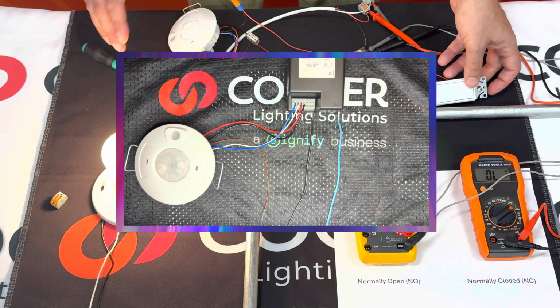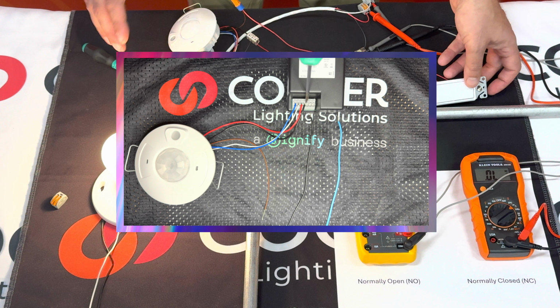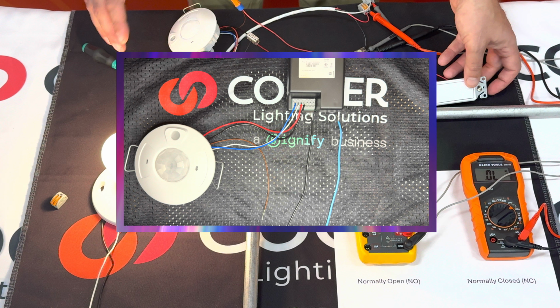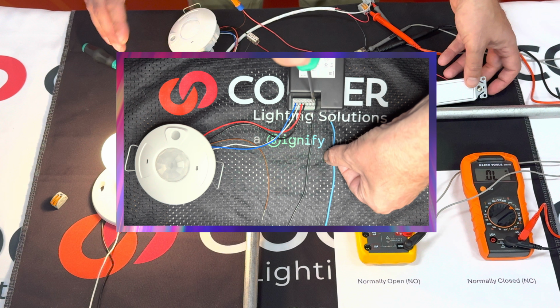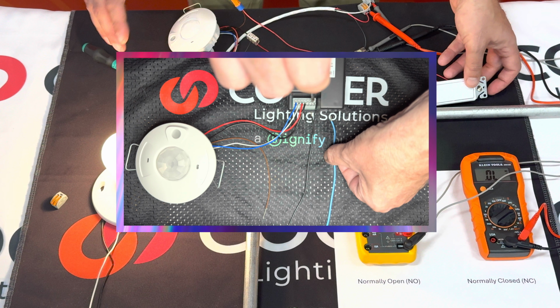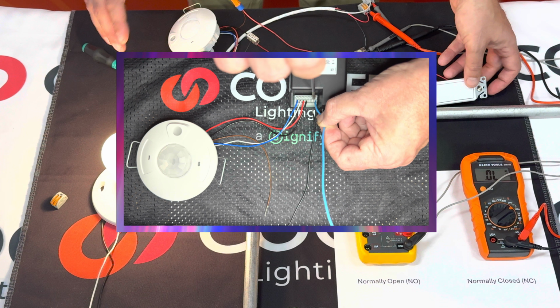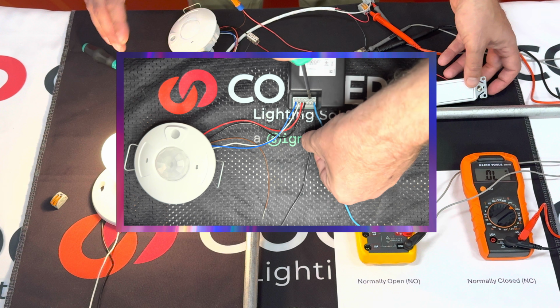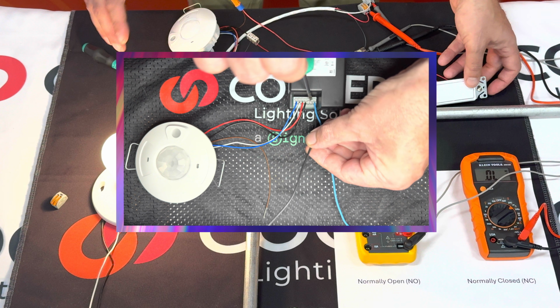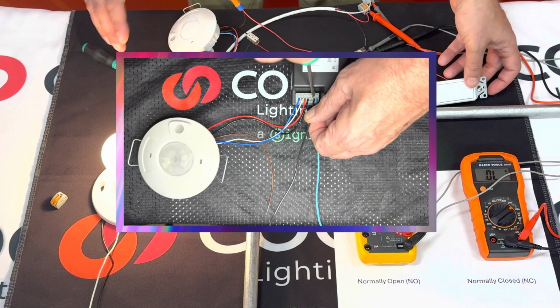BAS output wiring. There are two options for tracking occupancy using the BAS output on the RSP. Wiring to terminal 1 gives a normally open output. Wiring to terminal 3 gives a normally closed output. In this example, we are going to use the normally open BAS output. Wire the BASNO terminal 1 to the plus on the BAS controller input. Wire the BASCOM terminal 2 to the common on the BAS controller input.